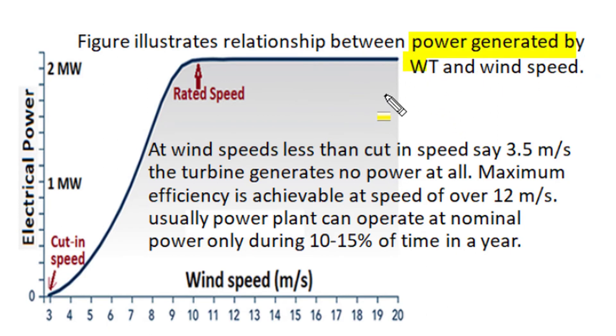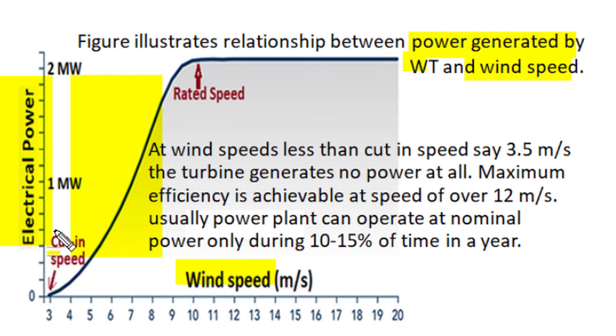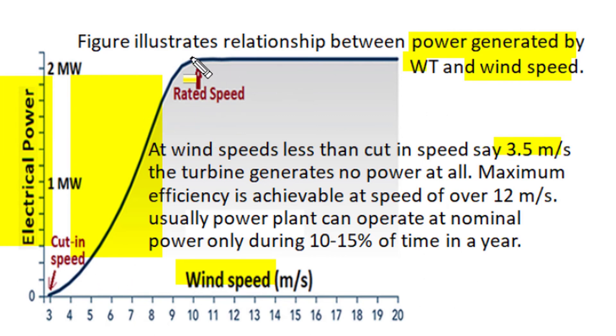Theoretically, power generated by a wind turbine is directly proportional to the cube of wind speed, but this is not true for low wind speeds. At wind speeds less than 3 or 3.5 meters per second, the turbine generates no power at all. The minimum speed above which the turbine can produce electrical output is called the cut-in speed, and typically the cut-in speed is 3.5 meters per second for utility-size wind turbines.